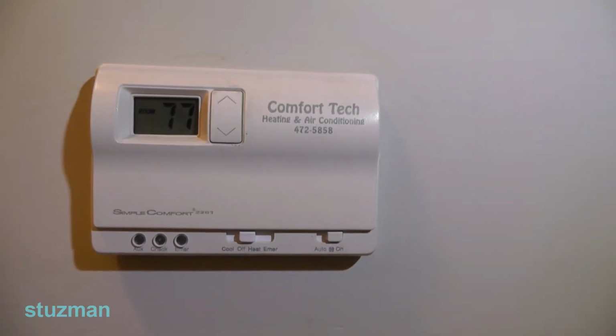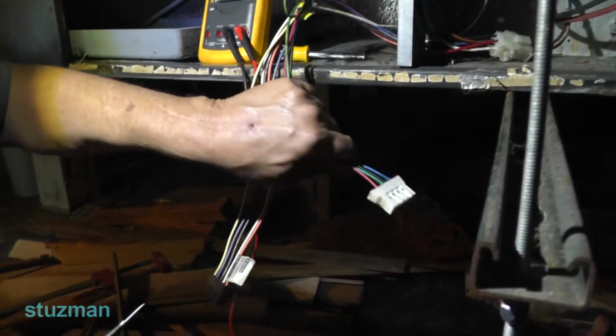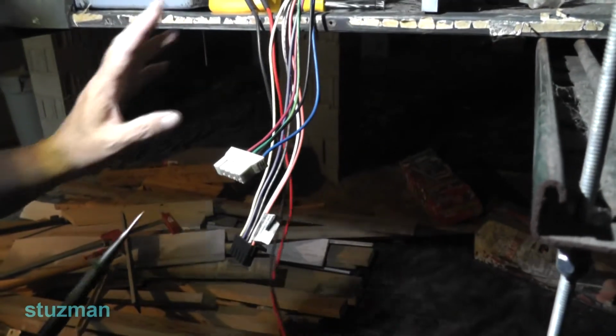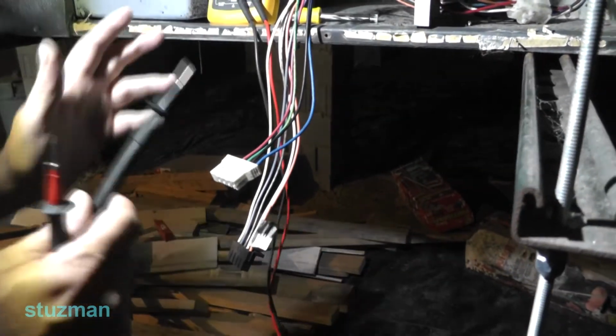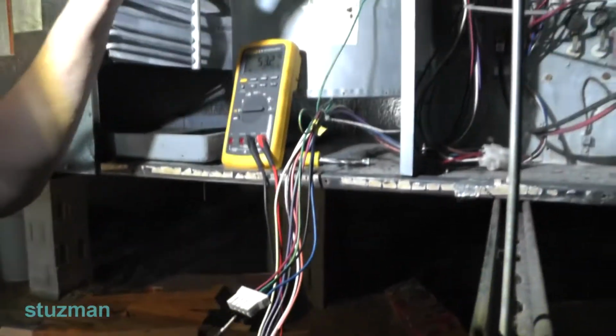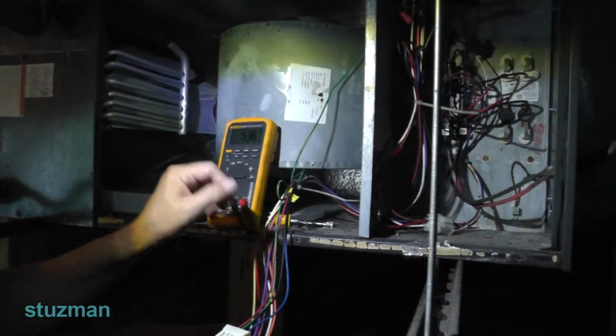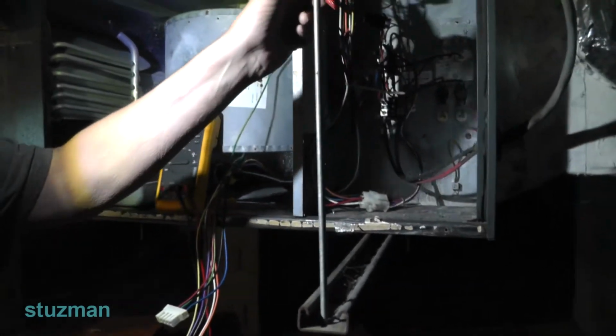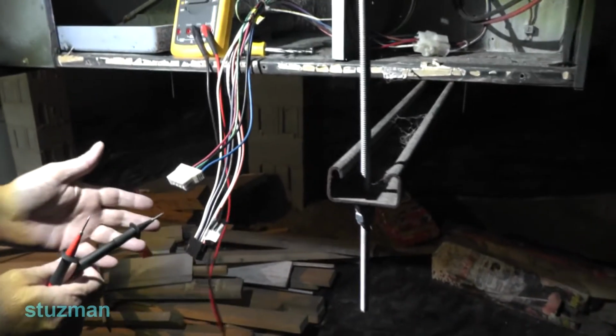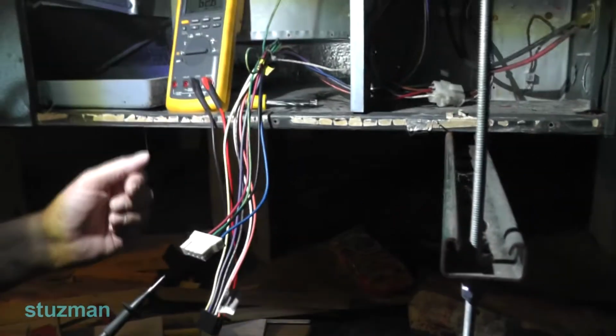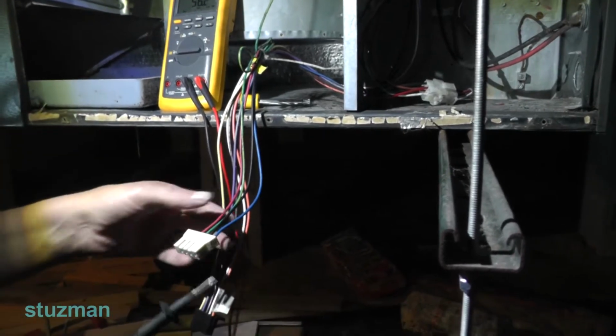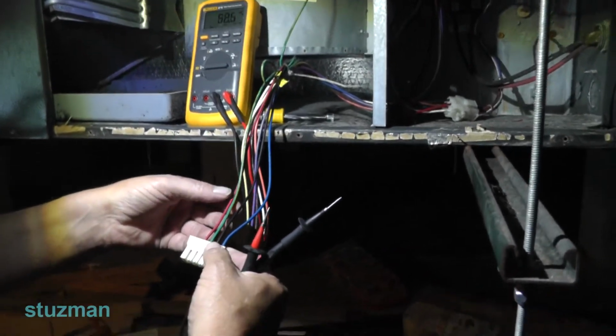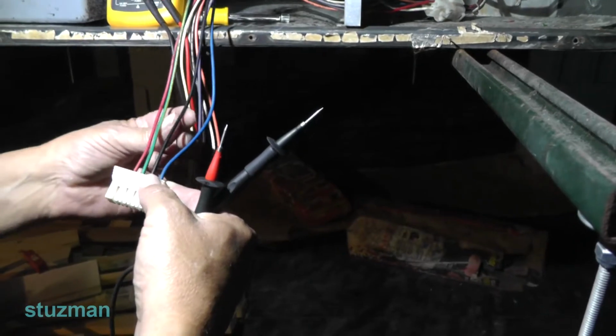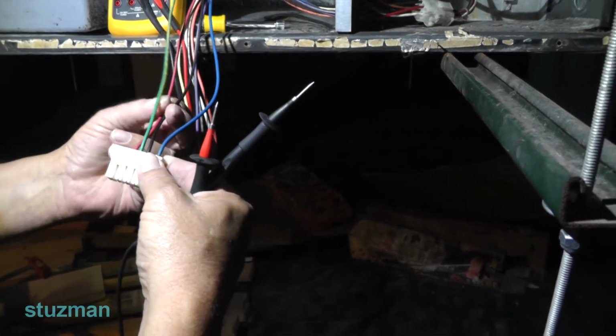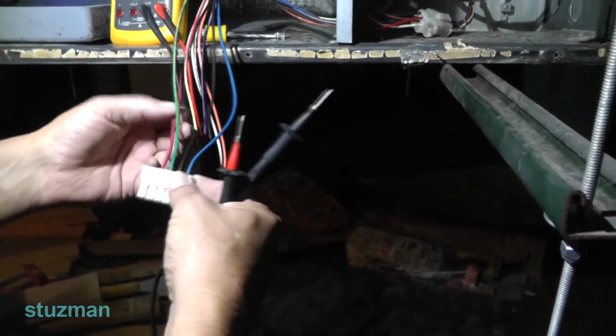Let's do some voltage checks. All right, so now all of our stuff should be hot down here going to the motor. Now unplug these connectors, because it's very difficult to back probe these things. You could do it over here on the terminal strip, but just to play it safe, we're going to go right to the connector itself. The first thing I'm going to check is the 240 volts, which should be live all the time. That is coming in on the red wire and the black wire. There's our 240 volts. The green is equipment ground.